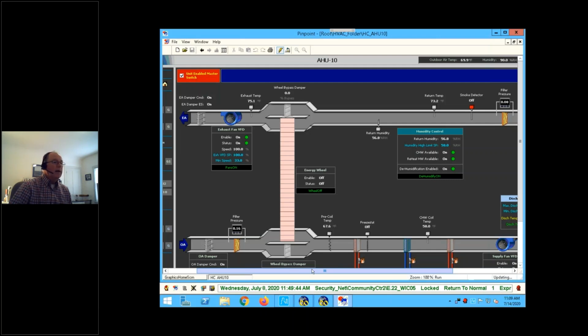So our outside air temperature, you said, was 69.9. I see. As our air comes in, looks like it's going through the wheel. I don't see that the dampers are open to bypass the wheel. Are they supposed to be open?